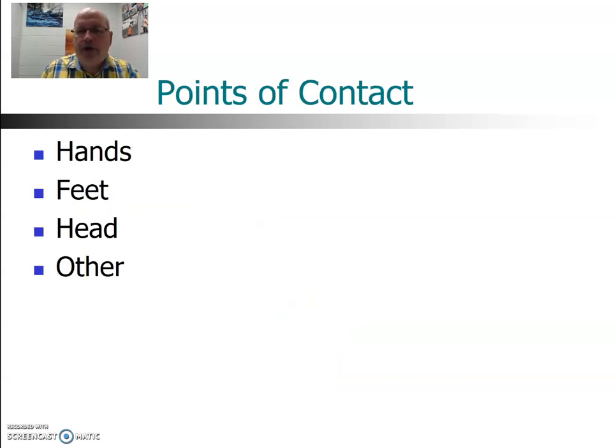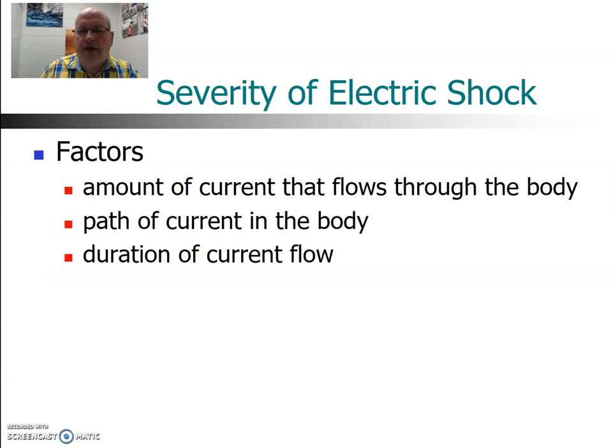The most common points of contact are your hands and feet, but it might be other things, like your head—maybe you're working on an overhead light fixture and stand up so your head touches a bare wire. It can also be other parts of your body. For example, I know of a case where a technician touched high voltage and the second point of contact was his belt buckle—he was leaning against a grounded workbench and got grounded through the buckle. So be aware it's any two points on your body, not just hands and feet.